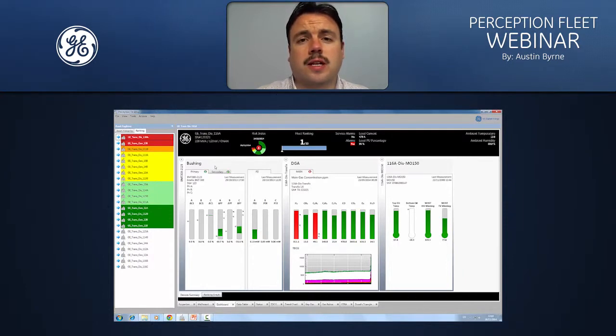Within the header of the transformer dashboard then, you can see we have the transformer information, so we have the name, the serial number, and the rated voltage information of the asset. We have our risk index circle, which shows you the risk index journey of the asset over a 9-month period. So you can see 9 months ago this asset was in good condition, it was a risk index of 1, and then over time a fault started to occur and the risk evaluation changed and it went up. So you can see it went to risk index of 2, then the issue seemed to correct and went back to risk index of 1, but then the fault spiral continued until the asset is now in its final risk index, which is risk index of 5.